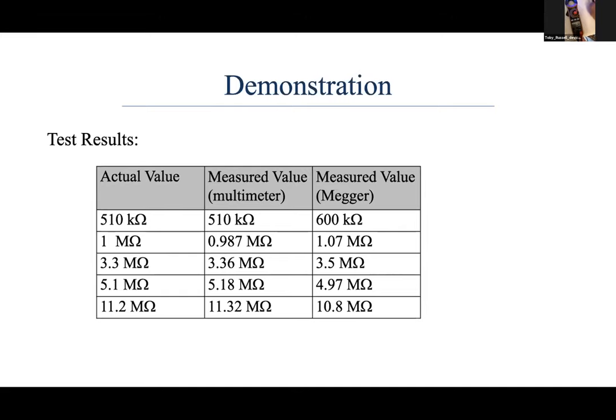This is the 500 volt test voltage. To apply the test voltage, you hit the switch and it's temporary. The light comes on and it shows the test voltage at about 529 volts. Can you show the meter? All right, now I will change the mode of the power supply to the 250 volt test voltage. And then when I apply the voltage, 248, right where it's supposed to be.